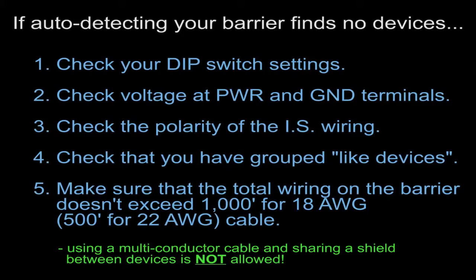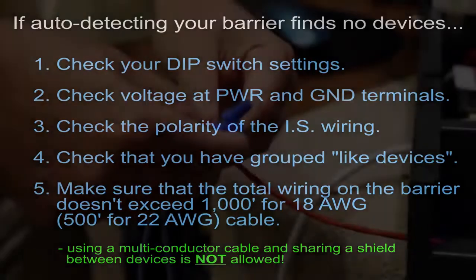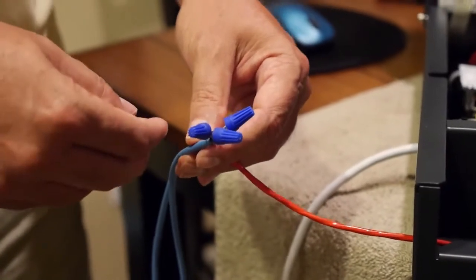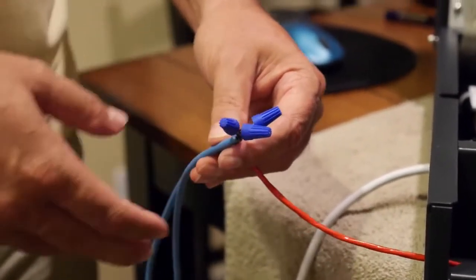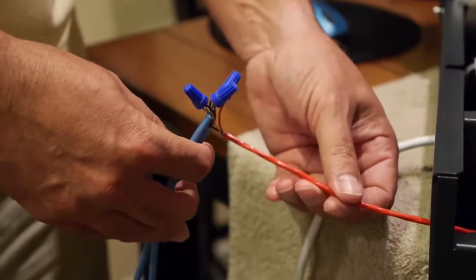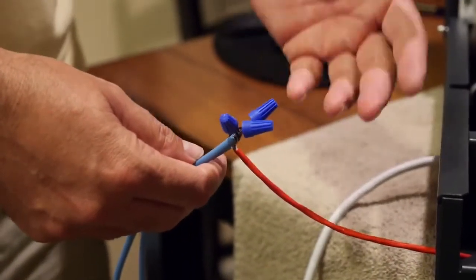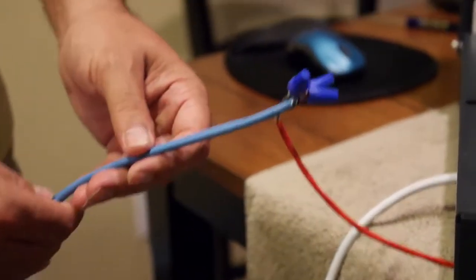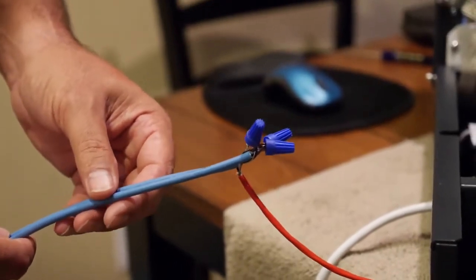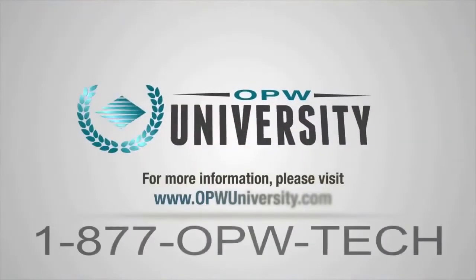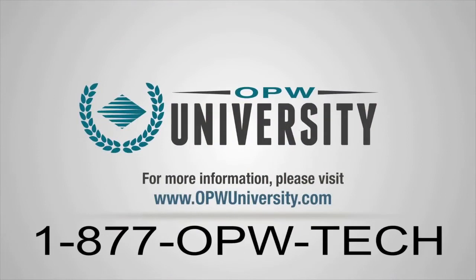If you're having problems doing the auto detect, go back out in the field and disconnect some of your devices. Connect them one at a time and make sure that you actually have voltage on all of your home runs back, and then see what you can find, because you might be exceeding the 1,000 foot or the 500 foot limitation. If this isn't the case, go ahead and call tech support and see if they can step you through a couple more troubleshooting techniques.